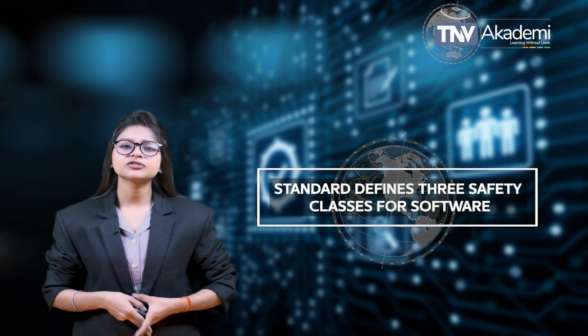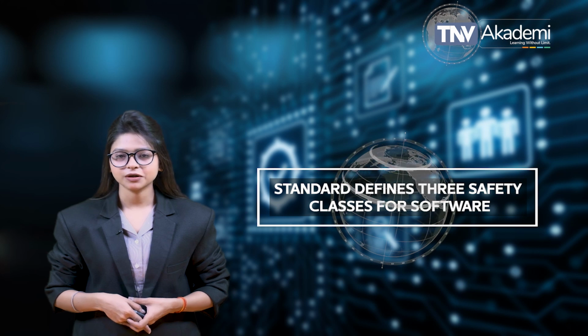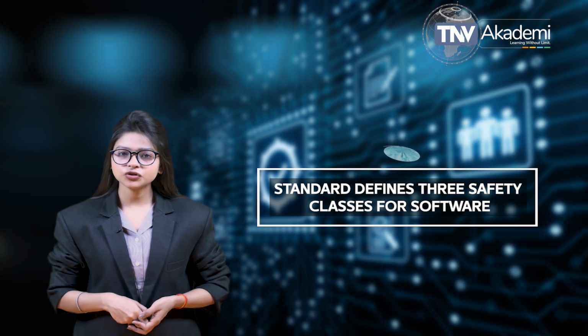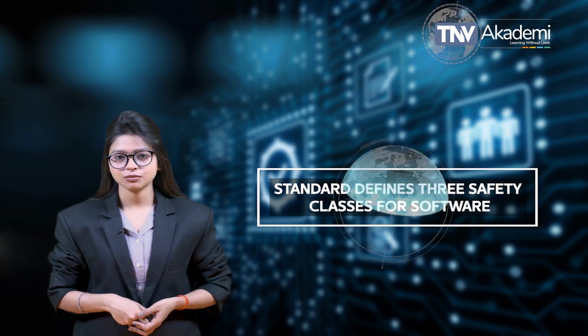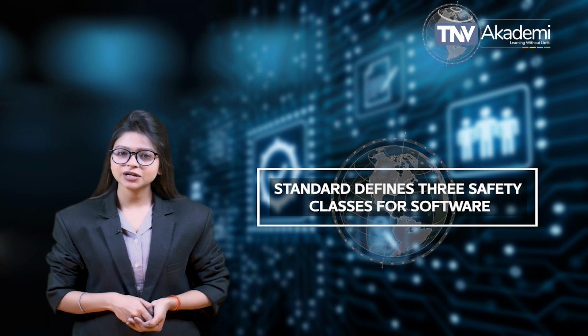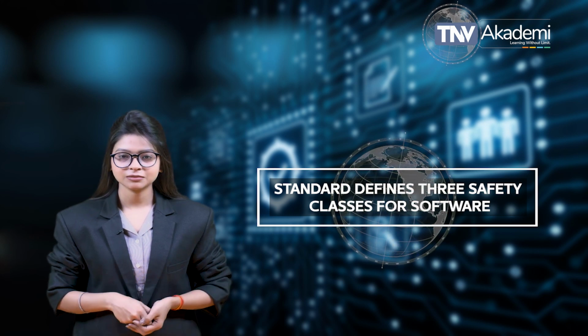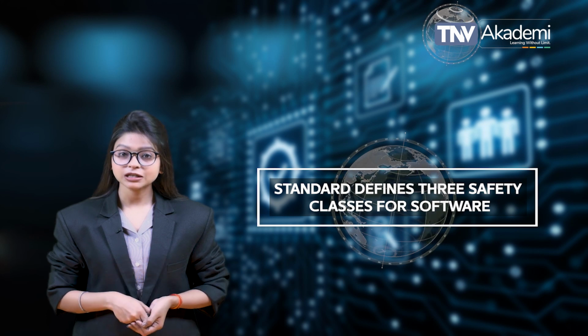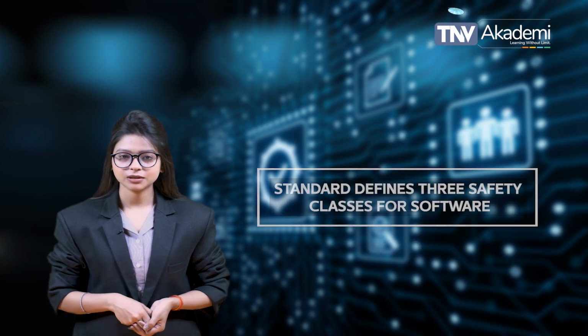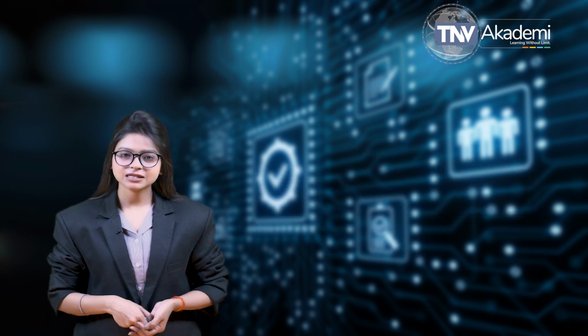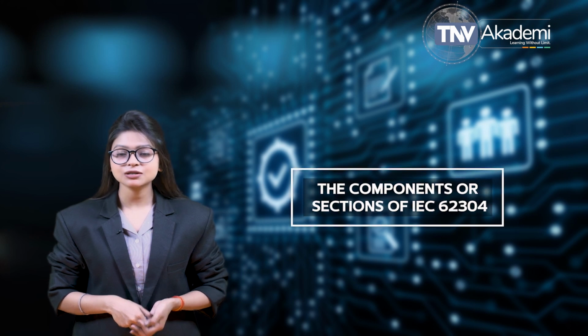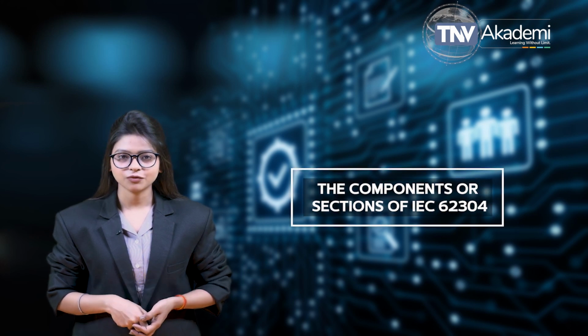The standard defines three safety classes for software. Class A: no injury or damage to health is possible. Class B: injury is possible but not serious. Class C: death or serious injury is possible. So we will now discuss the components or sections of IEC 62304.